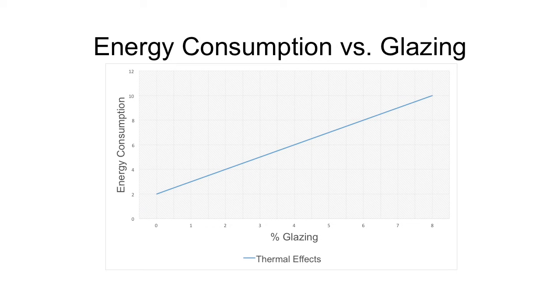Very simplistically, from a thermal perspective, the more glazing we have, the higher energy consumption. Because as we have more glazing, glazing typically is not as high performing as the opaque portions of the envelope, and so we've got increased heat loss during the winter, increased heat gain during the summer, as well as increased heat gain from transmission and through direct solar heat gain through the glazing. So pretty linear: as we get more glazing, more energy consumption.